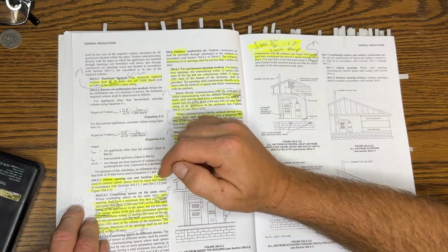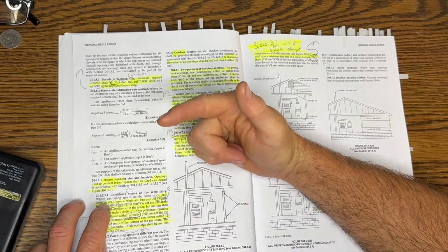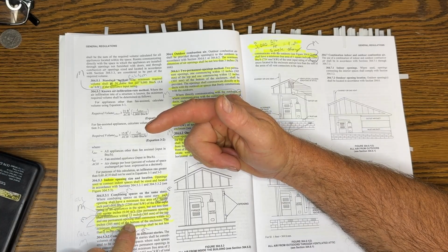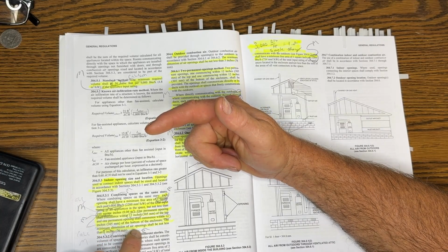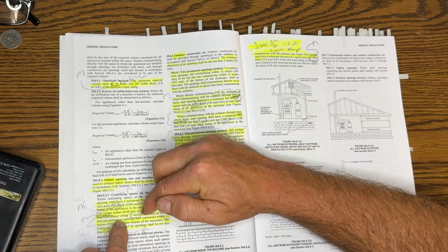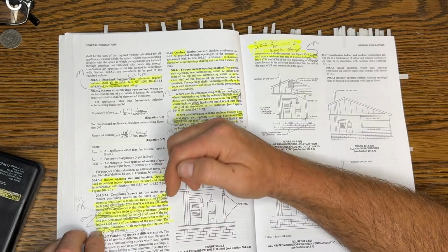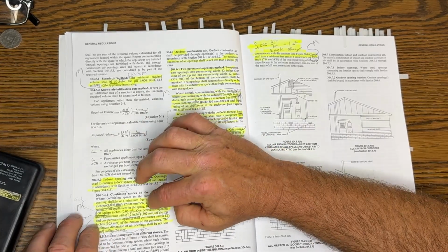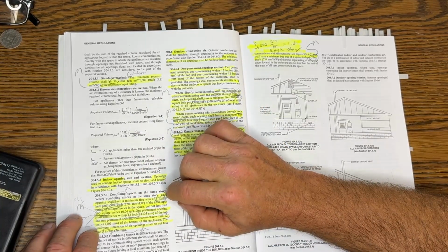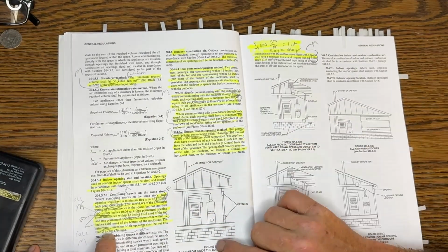But what I'm getting at is, the magic number is 100 square inches as a minimum, 1 square inch per 1,000 BTU, and 12 inches from the bottom of the enclosure. Okay, I guess it is 2. One permanent opening shall commence within 12 inches of the top and one permanent opening at the bottom. So I guess you do need top and bottom. It's been a while since I installed one of these, and it's been probably 6 months since I took this test, so bear with me. I can't remember exactly what I had here, but just read that, you'll figure it out. Minimum dimension is 3 inches, okay?